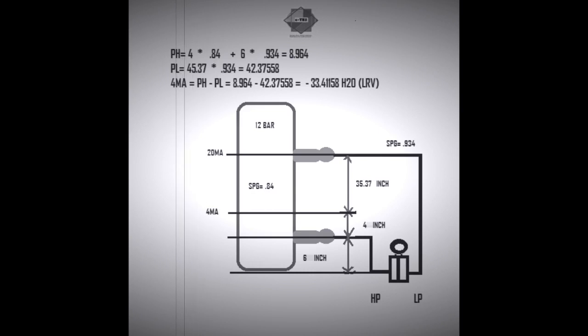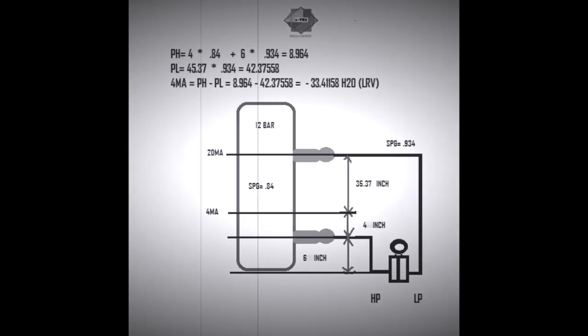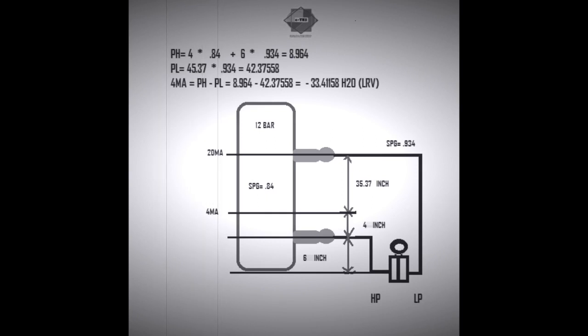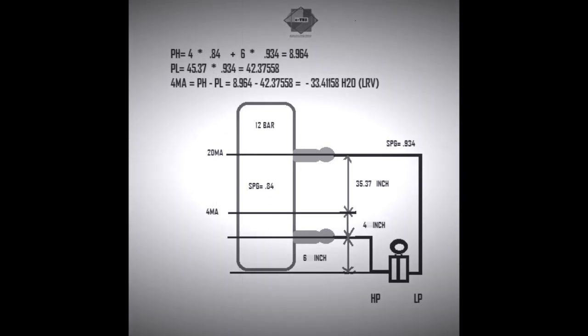Now we find PL from the height of the capillary tube mounted on the LP side. The total capillary tube height from tapping to the transmitter is 45.37 inches multiplied by 0.934, the specific gravity of the liquid-filled capillary, giving us PL = 42.37558. So PH minus PL is 8.964 minus 42.37558, giving us LRV = minus 33.41158 inches of water column.